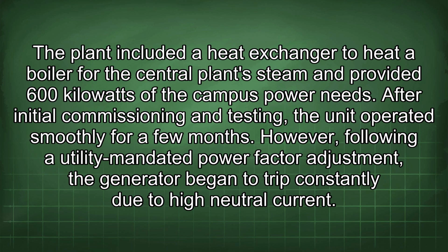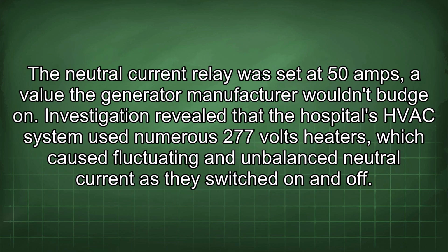the campus power needs. After initial commissioning and testing, the unit operated smoothly for a few months. However, following a utility-mandated power factor adjustment, the generator began to trip constantly due to high neutral current. The neutral current relay was set at 50 amps, a value the generator manufacturer wouldn't budge on. Investigation revealed that the hospital's HVAC system used numerous 277 volt heaters, which caused fluctuating and unbalanced neutral current as they switched on and off.